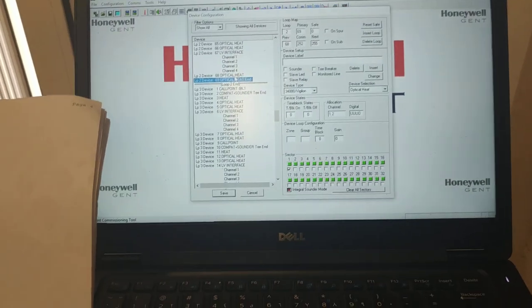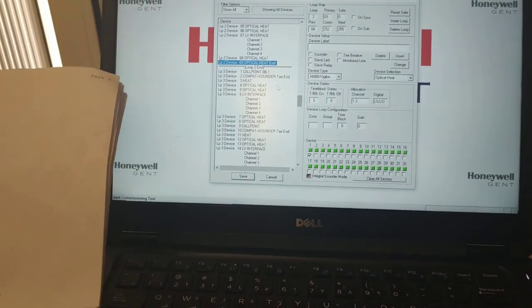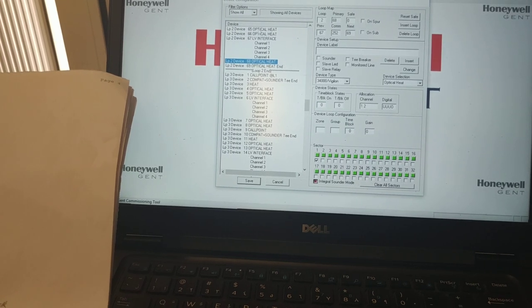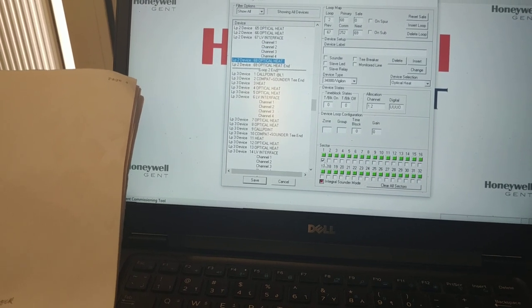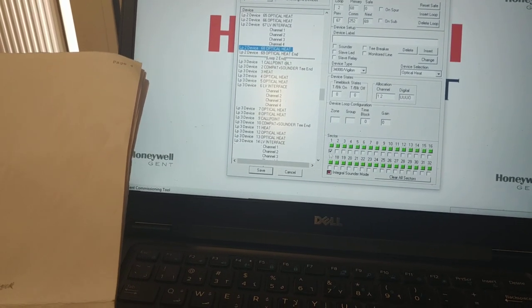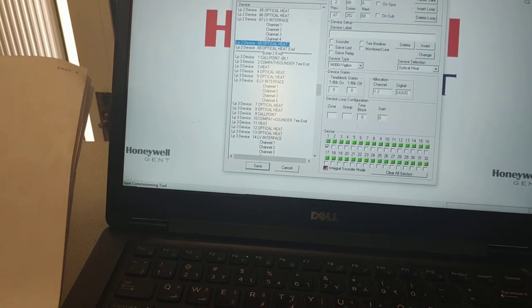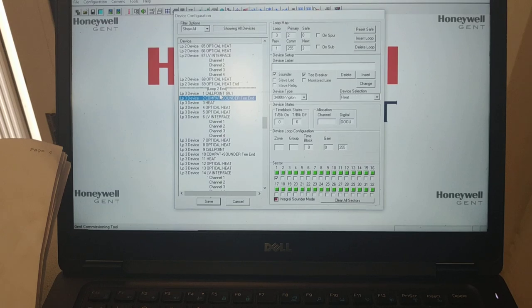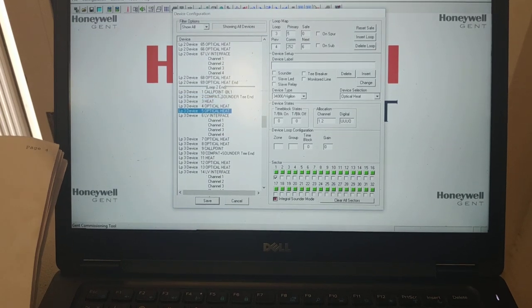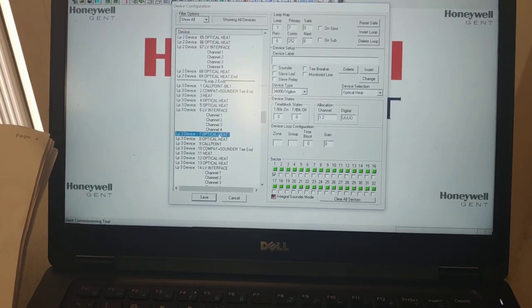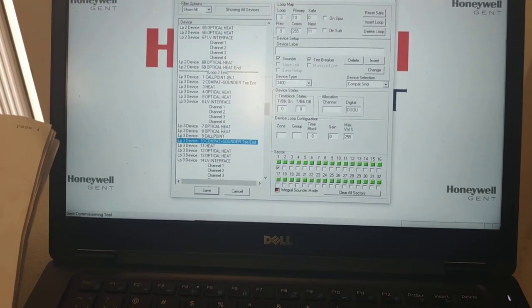Loop 2 is 69 devices. We need to check why there are no labels and both are Sector 1. Sector 1 is programmed as the input here. Loop 3 also has no labels — all in Sector 1.